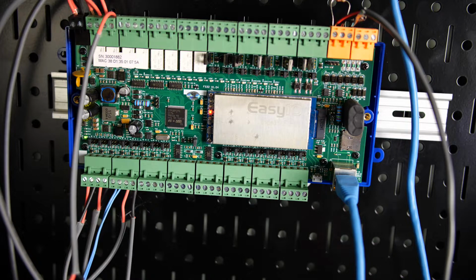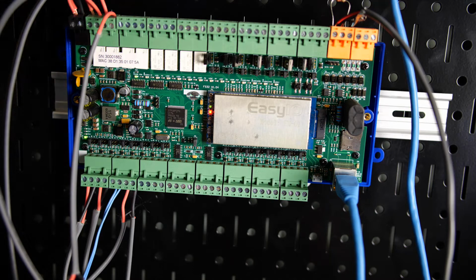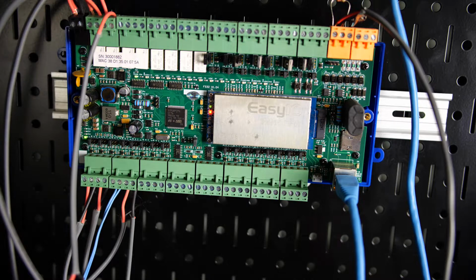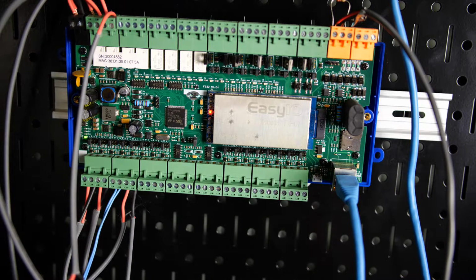So in day 1 we talked about BAS just overall. In day 2 we talked about inputs, and today in day 3 we're going to talk about outputs. When we talk about outputs, there's really 4 kinds of outputs we're focused on. We're focused on internally sourced outputs, externally sourced outputs, and both of those are digital outputs. We'll talk about what that is in just a second. We're talking about voltage outputs, and we're talking about amperage outputs. Sure, there's other types of outputs. There's floating outputs, things like that, but ultimately floating outputs are just a version of internally sourced outputs where you use 2 of them. Alright, so what are outputs?